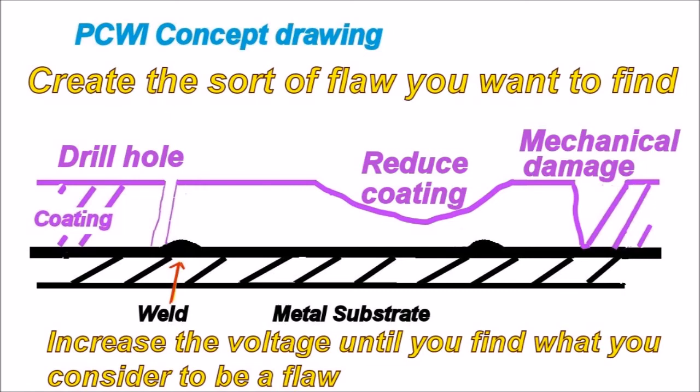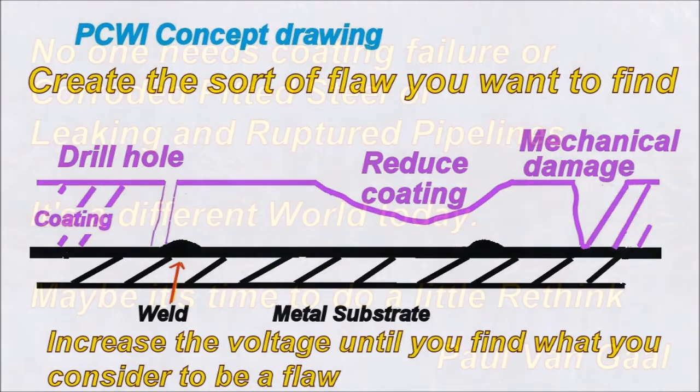Then you can also reduce the coating thickness and keep passing the probe over it until you actually burn through. It depends really what you're looking for as to what you consider as a flaw. You can mechanically damage it and then run the coil over it and keep increasing the voltage until you ultimately find it as a flaw. It's just something I think you should really be looking at.